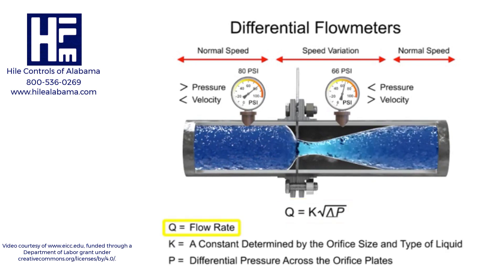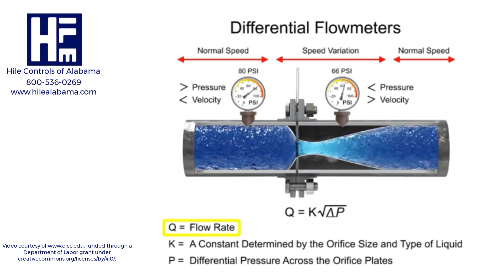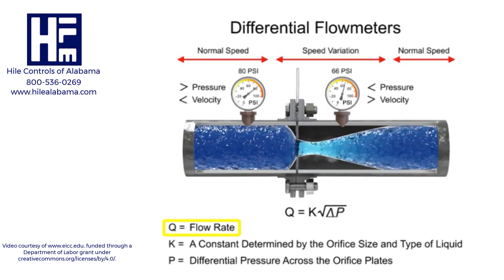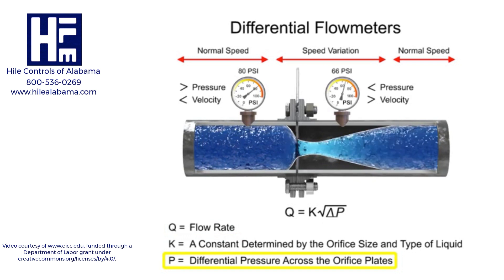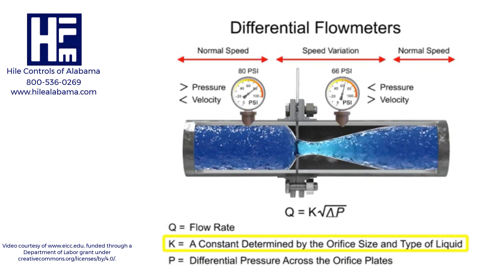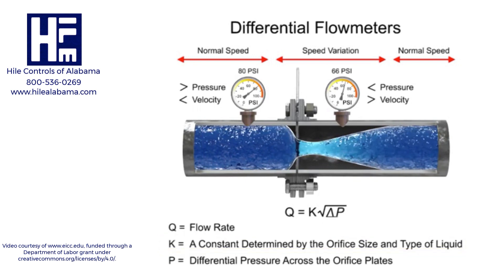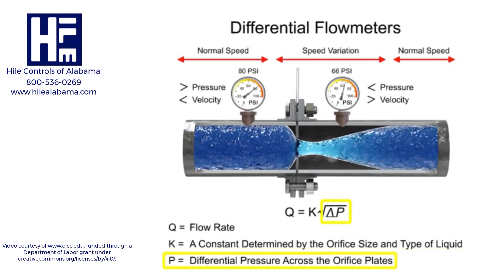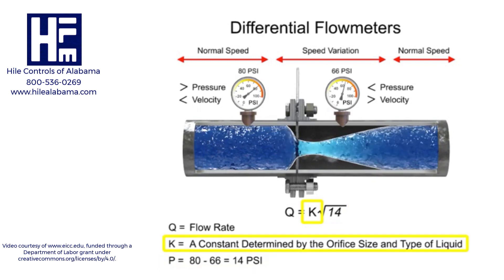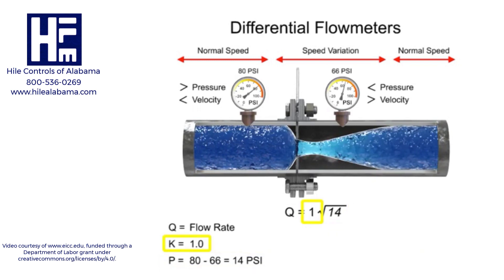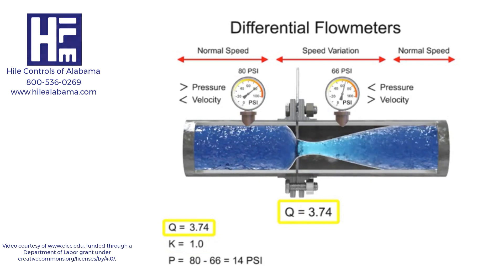The flow rate, Q, of a fluid through an orifice plate increases in proportion to the square root of the pressure difference on each side multiplied by the K factor. For example, if the differential pressure increases by 14 PSI with a K factor of 1, the flow rate is increased by 3.74.